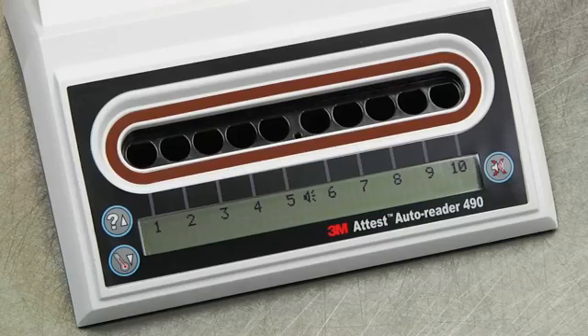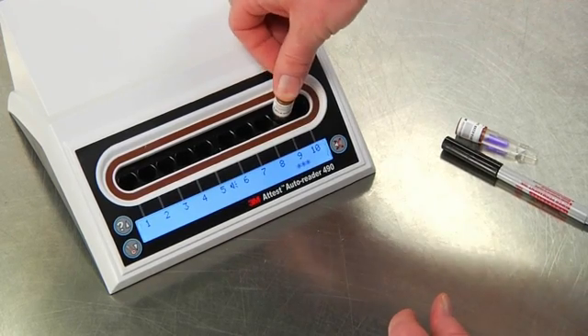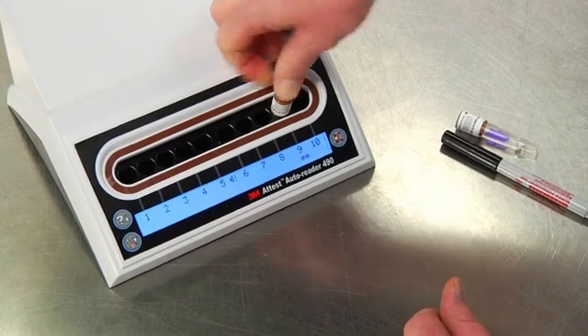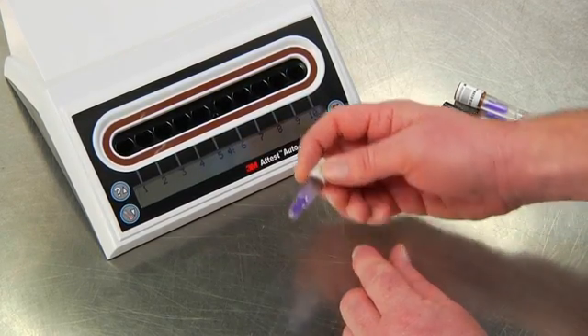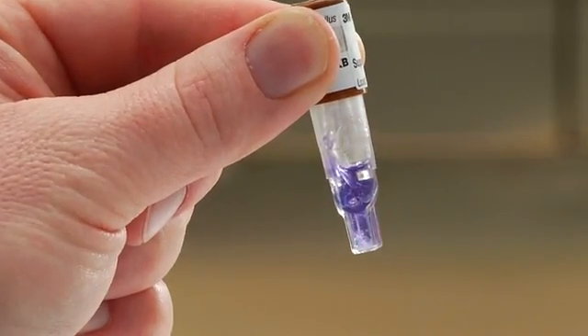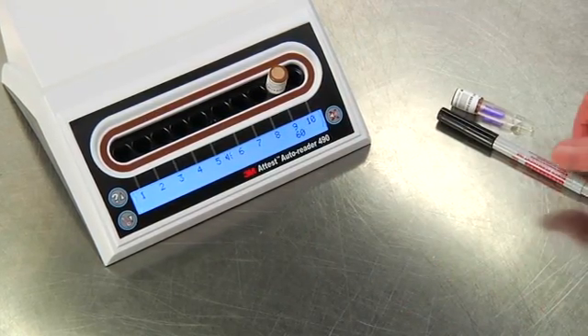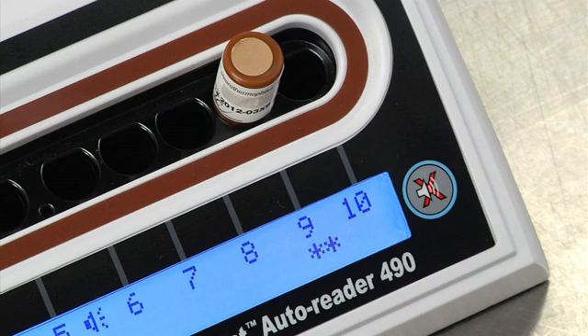Wearing safety glasses, place the Attest SuperRapid BI in a matching color-coded Attest Auto Reader 490 incubation well. Make sure the flat side of the vial faces the back of the Auto Reader. Press the cap of the Attest SuperRapid BI down firmly to close the cap and crush the glass ampule. Immediately remove the BI and visually verify that the glass ampule has been crushed. Then flick the vial to cause the purple growth media to flow to the growth chamber at the bottom of the vial. Return the activated BI to the incubation well and check the LCD panel to confirm that the vial is properly seated. The Auto Reader LCD panel will display a series of asterisks, then the remaining incubation minutes right below the incubating BI.